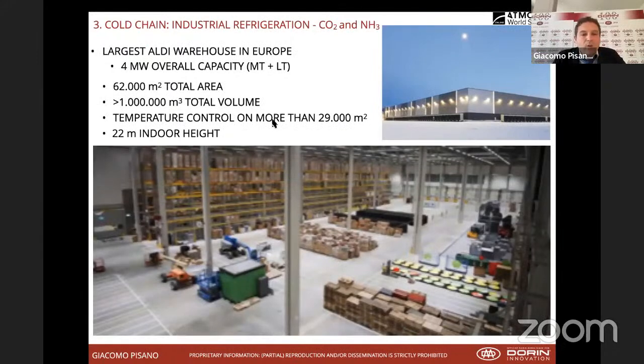Just to give you an idea where CO2 is successfully used in very large equipment, this is the largest Aldi warehouse in Europe, featuring 4 megawatt duty between medium temperature and low temperature load, for a total surface of 62,000 square meters, where we have temperature control on more than 29,000 square meters. And this warehouse features 22 meters indoor height. So it's really a monster equipment done with CO2 transcritical technology.